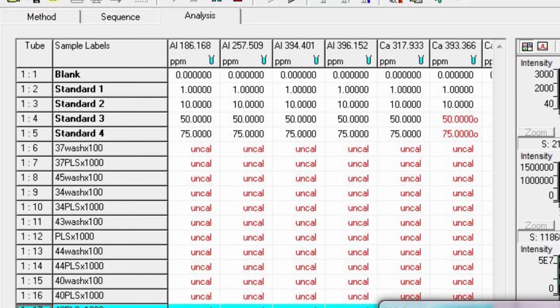Each wavelength has a different sensitivity, and this means the particular wavelength exceeds the maximum intensity and is not a good choice for your concentration range of interest. The word "uncal" for your sample output means that the calibration line did not automatically fit the data to within 5%. Most users have high and low ppm concentrations of their samples.